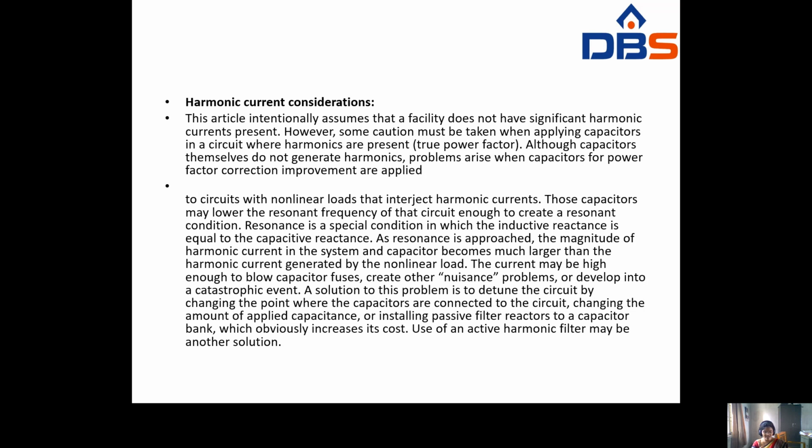So for any system, you have to connect a load. Whenever it reaches the resonance condition, the harmonic current in the capacitor becomes much larger than the harmonic current generated by the non-linear load. The current may be high enough to blow capacitor fuses or create nuisance problems.